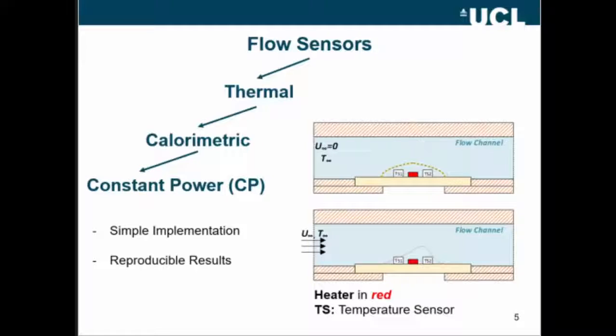Most of the thermal flow sensors, including the calorimetric, have modes of operation. This basically means how you deliver the power to the heater. One of them, the one that we use here is the constant power. Really simple. You have to deliver the same power all the time, no matter the fluid's velocity.